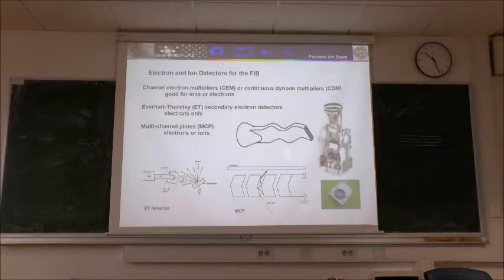Then we need some piece of plastic, optically very good, a light guide, because its function is to suppress the electrons. Maybe some electrons could pass this scintillator, and we must not ruin the photomultiplier, because one high energetic electron could destroy it. It's a very sensitive piece of this detector, and the light that is emitted in the scintillator is just multiplied with this photomultiplier. And at the end, we get the signal. If we have a small amount of electrons here, the signal will be low. If we have a large amount of electrons, the signal will be high.